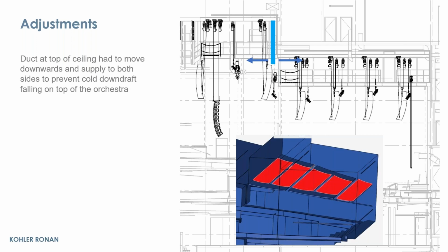Again, looking at those configurations, you can see over here the acoustical baffles are open, and at the bottom you can see those baffles are closed. So a lot of things were changing continuously. This is a very dynamic space, and we had to test multiple different configurations, making sure our design worked for all of them. It was fairly challenging as we went through the whole process.